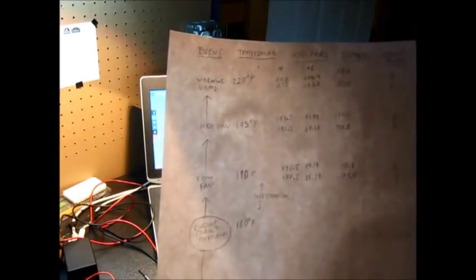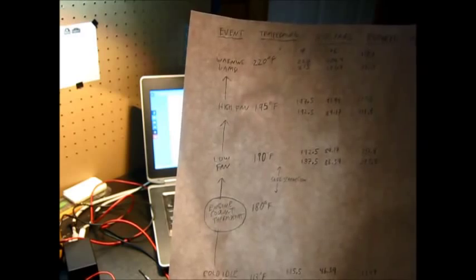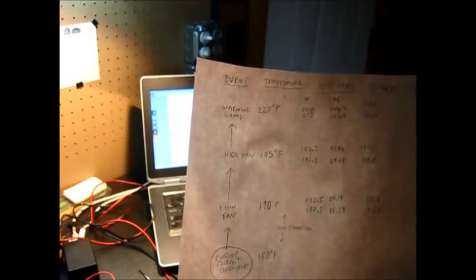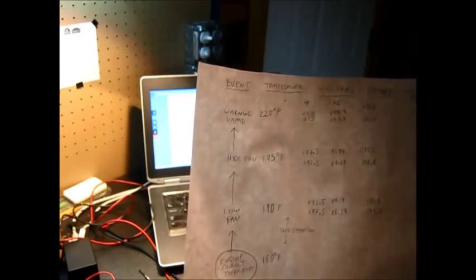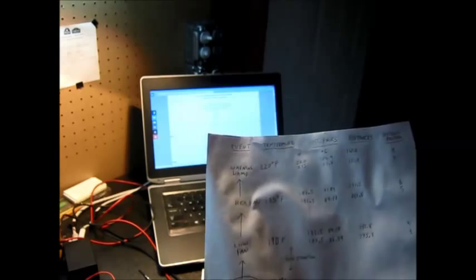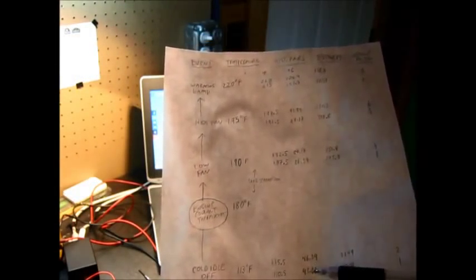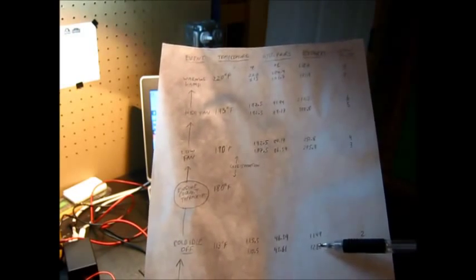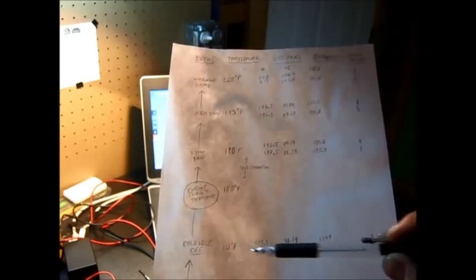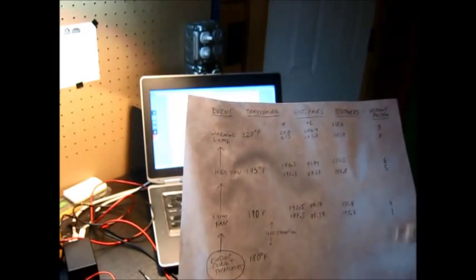And it's exactly for this. It lets you take a chart like this, where you've got a value in between two of the chart entries. And you need to know what the exact value would be. So for each of these points that I've come up with, the 43.61 degrees C, using this formula in the sensor chart, I came out with 1286 ohms. And the same thing for each one. So at this resistance, when the temperature sensor resistance falls to 1286, then we know we're at this event. It falls to 1149, it's at this event, and so forth up the chart. Because this controller, it doesn't actually know temperature. It only knows electrical parameters. So we're going to have to give it a voltage and let that voltage tell it where the temperature is. So all this right now is a means to an end.